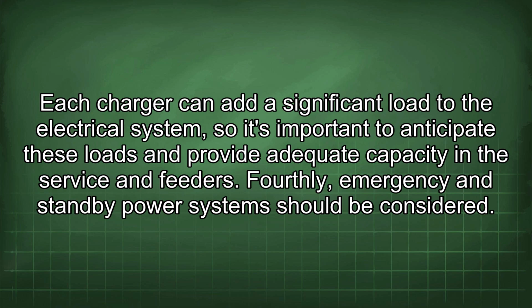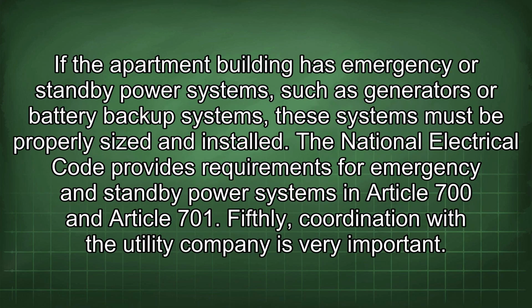Fourthly, emergency and standby power systems should be considered. If the apartment building has emergency or standby power systems, such as generators or battery backup systems, these systems must be properly sized and installed. The National Electrical Code provides requirements for emergency and standby power systems in Article 700 and Article 701.